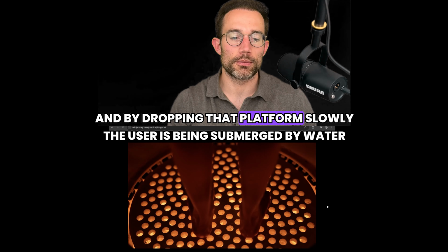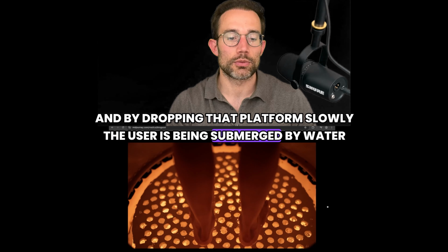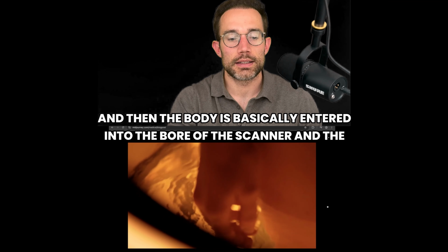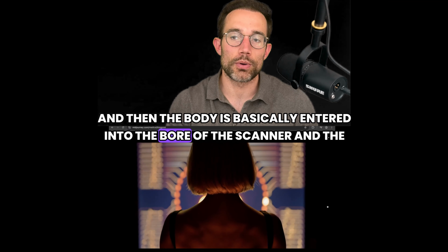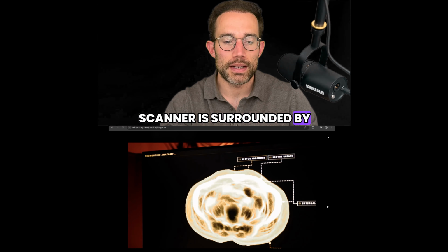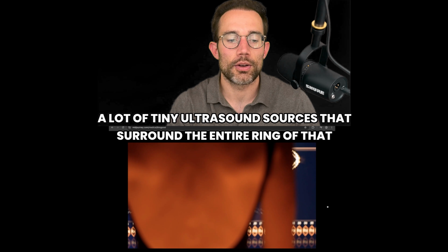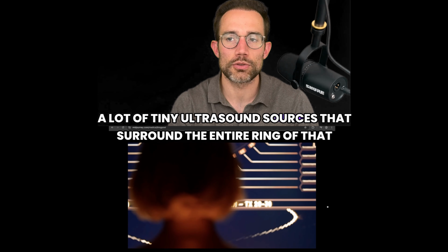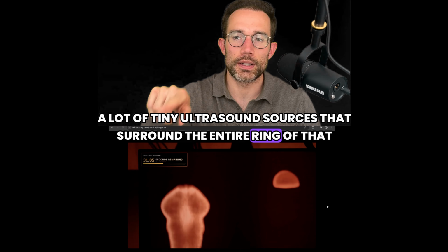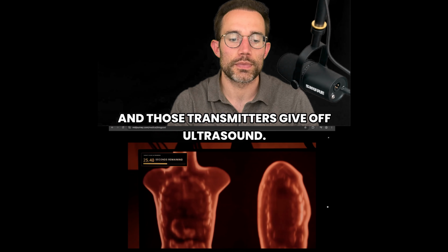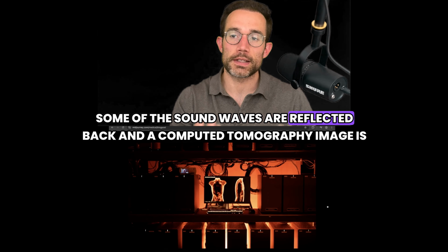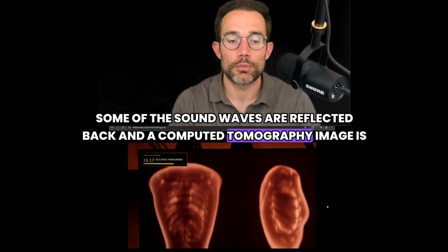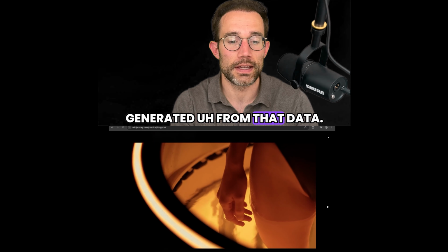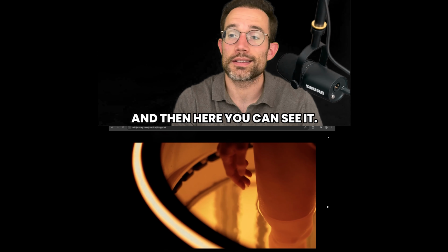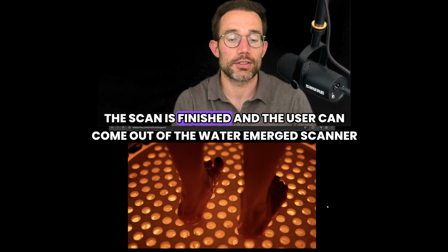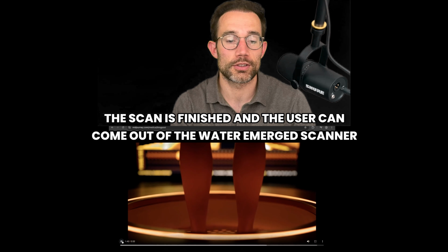And by dropping that platform slowly, the user is being submerged by water, and then the body is basically entered into the bore of the scanner, and the scanner is surrounded by a lot of tiny ultrasound sources that surround the entire ring of that scanner. And those transmitters give off ultrasound. Some of the sound waves are reflected back, and a computed tomography image is generated from that data. And then here you can see it. The scan is finished, and the user can come out of the water immersed scanner, and that's it.